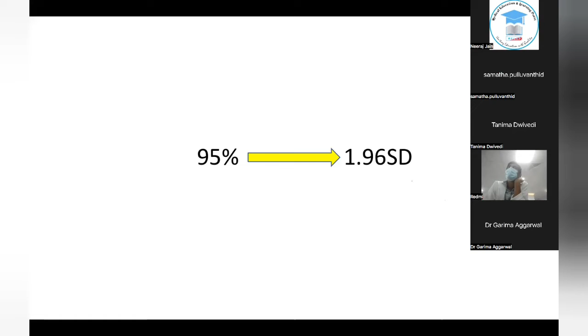So if you explain them this concept, they will also understand and they will take decisions accordingly. Suppose in the morning it is 49,000, in the evening it is 55,000, and the measurement uncertainty is 3,000. Whatever you are reporting as 49 can be 52, and whatever you are reporting in the evening as, suppose, 56,000 can be 53. You can say there is a little increase in the platelets. This information is useful for the laboratory to interpret results and for the clinicians also, so it shall be provided to clinicians on request.